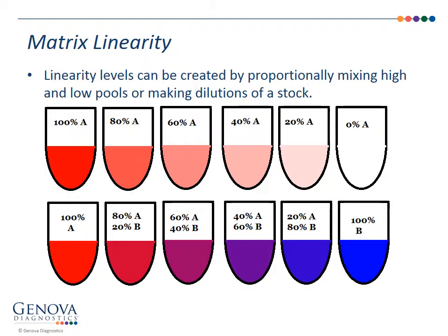If you see any differences between those two as far as the linearities, the CVs, the errors, then that's going to give you some clues about whether you're going to have any matrix effects or interferences, or if there's anything about your sample that's going to change the values of your analyte of interest. And at this point, it's helpful to know, and it's helpful to compare, and helpful to talk about, but it's going to be very informative as we get into more precision and accuracy experiments.